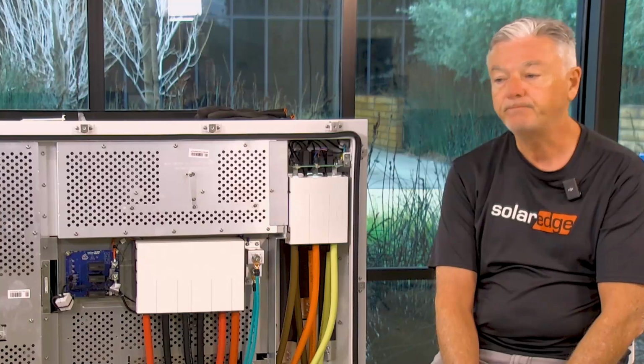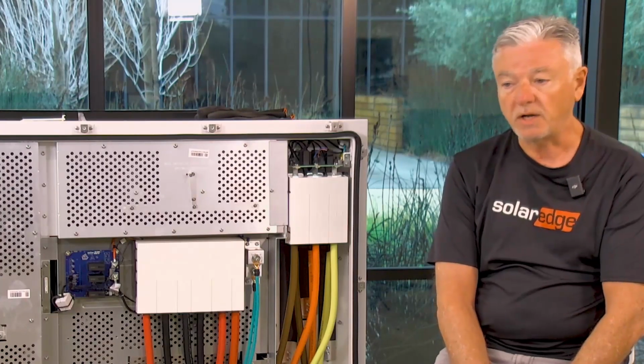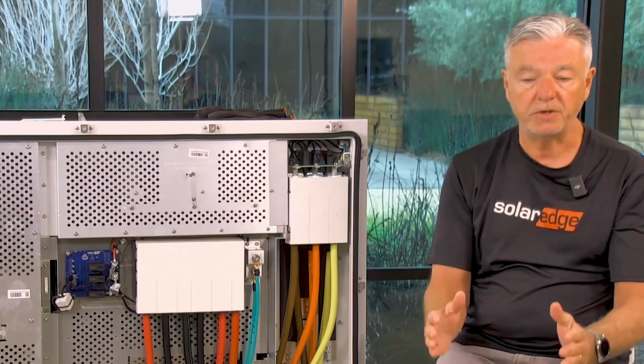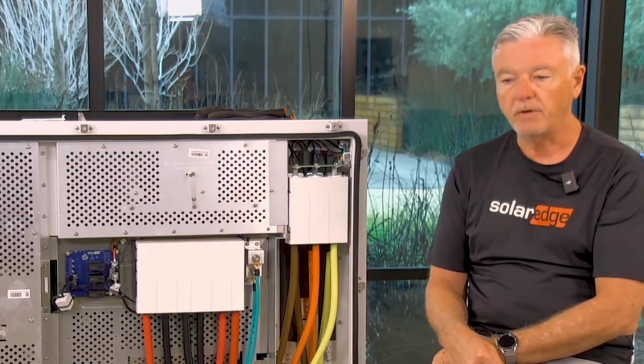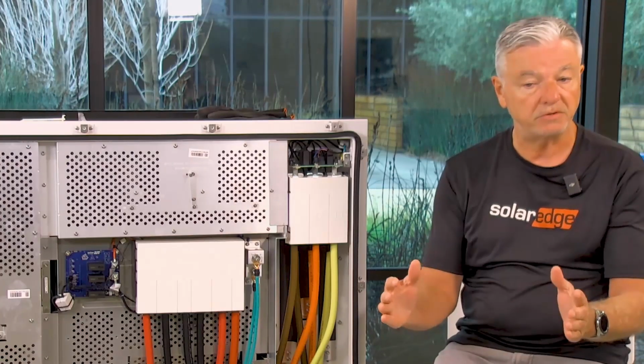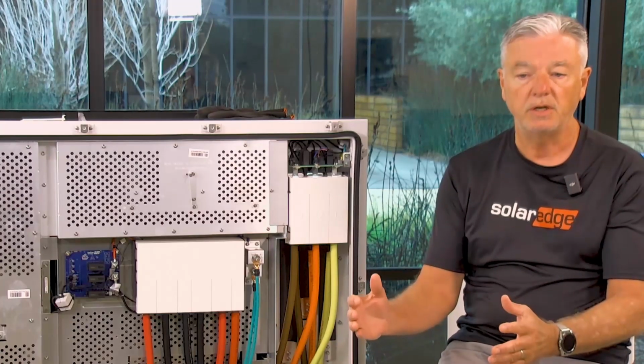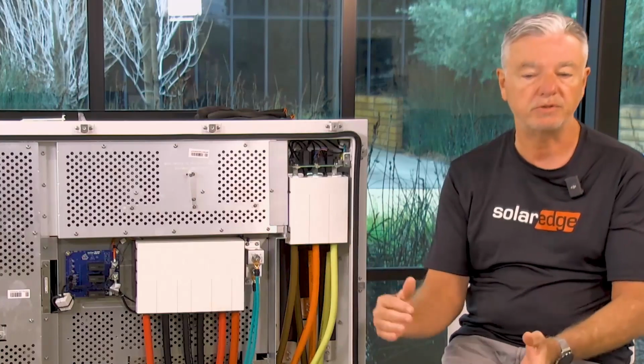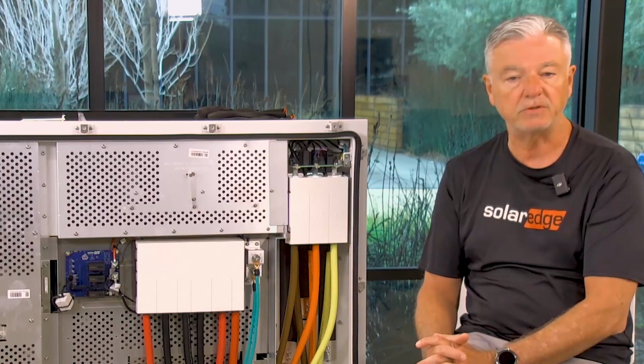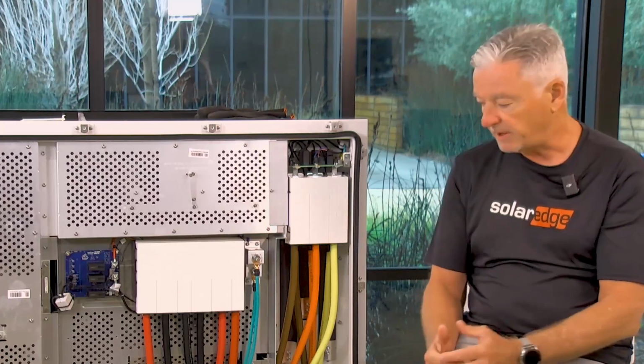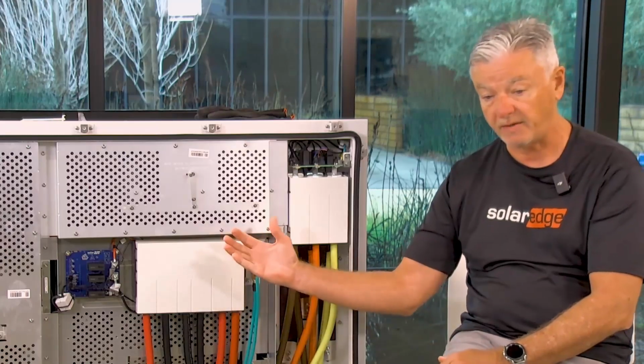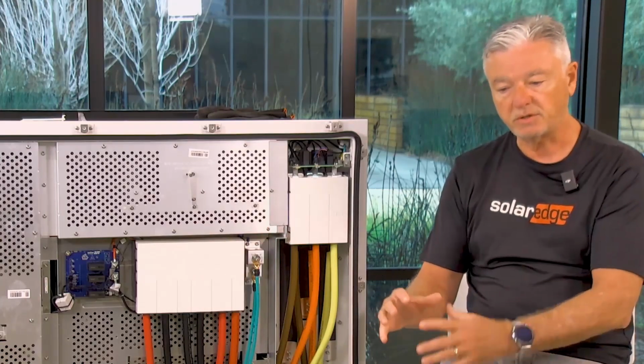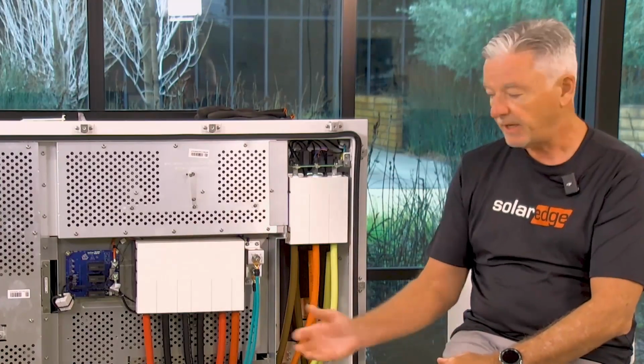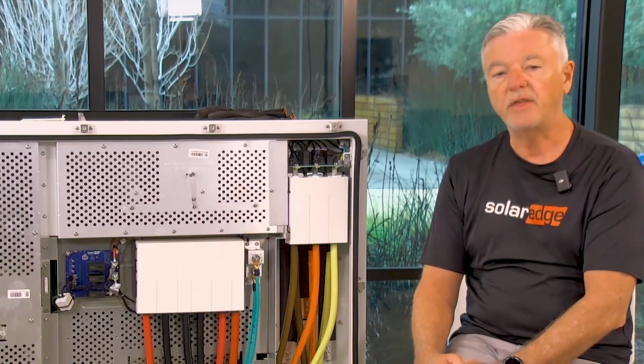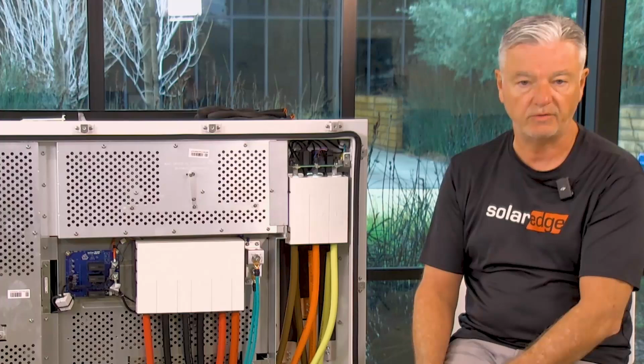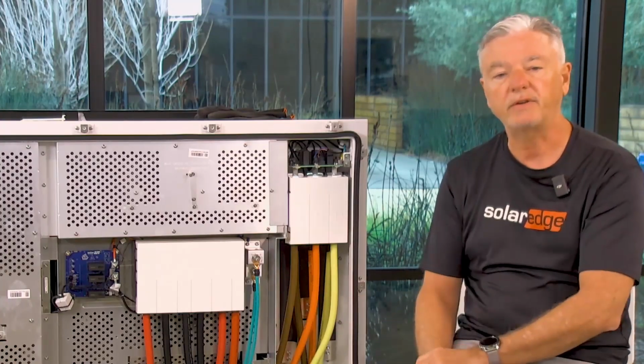Do you have any advice for design, and where can I find design resources? Yeah, so on our data sheet, for the H1300 optimizer that is used with this inverter, there are design rules that tell you how many optimizers you can have in a string, depending on the power class of your module. It tells you minimum numbers and then maximum power per string. So that determines the number of modules and optimizers you can have in a string. There are additional rules on that optimizer data sheet that tell you how many strings you can have attached to an inverter. So the minimum in order to have your longest strings is 14 strings, and then you can size it up to 200% oversizing. So that could be anywhere from 20 to 24 strings, depending on the power class of the module and how many strings you have connected.